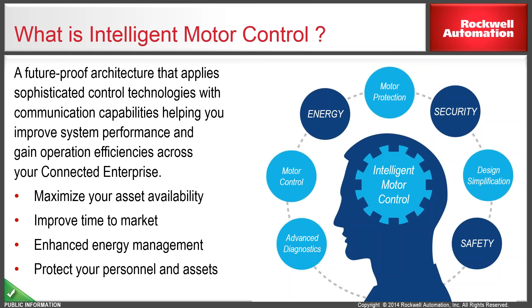This picture shows a graphical representation of the offering, where motor control devices have the ability to communicate over Ethernet/IP and work as an integral part of the control system. So now a motor control device can do much more: respond to interlocking commands, provide extremely valuable diagnostic information, and be configured as a natural extension of the system.